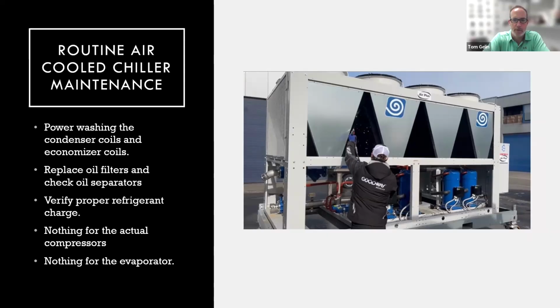From our quiz, we learned that it's important to clean our condenser coils, and if you also have an economizer coil, you need to clean that too. Why do we do that? If we're not condensing our refrigerant to a liquid, we're using additional compressor energy that we don't need to. So for your customers, you have to power wash the condenser coils and economizer coils if present. And of course, the oil maintenance needs to be taken care of, and the refrigerant charge needs to be inspected.